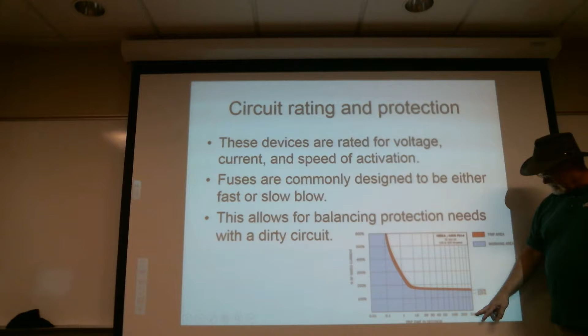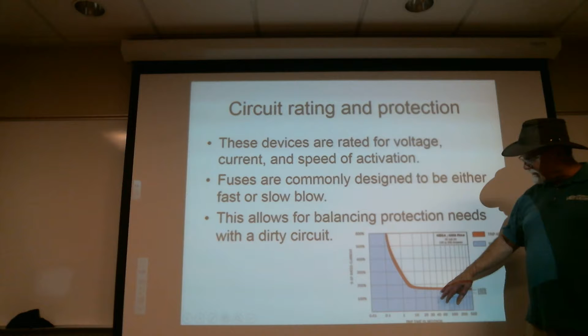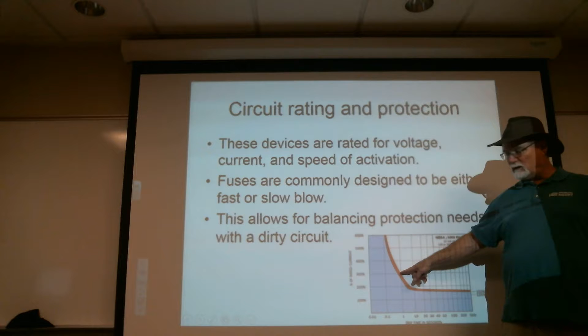A fuse, normal fuse or even slow blow fuse, you'll see in that chart the amount of time it takes to trip. If I'm at 100%, it's not going to trip. At 125, it may not trip. At 150, it's going to take about 500 seconds to go. Somewhere sort of above that, it's like dropping off. I can be at 300% of the fuse capacity, and it'll still go for a whole second before it blows. That's going to be a pretty slow acting device. They make them where they're way, way quicker. The top end of that chart is that 500, that might be 500 milliseconds or half a second. And all the way down in there, you're getting into the millionth of a second. So we've got some really, really high speed ones.